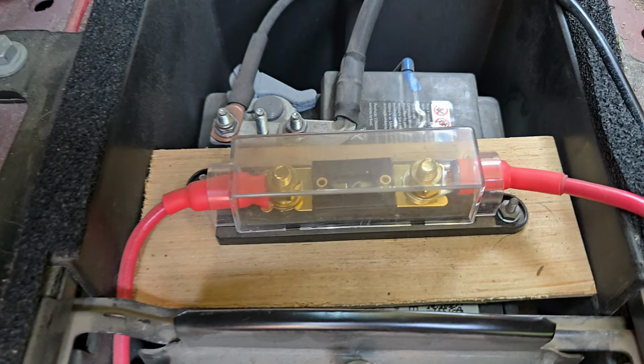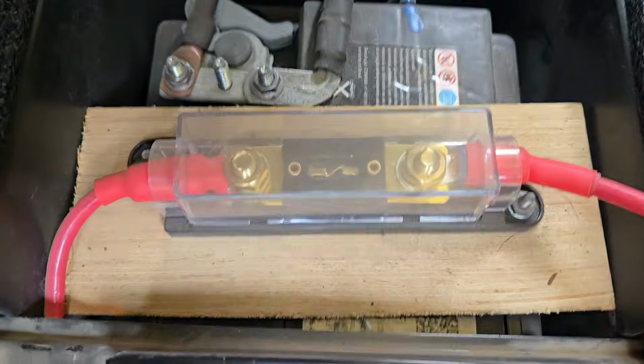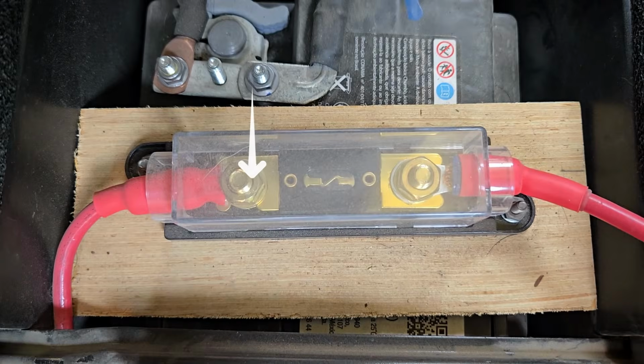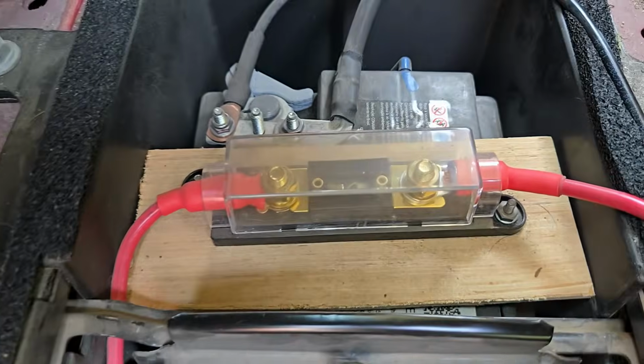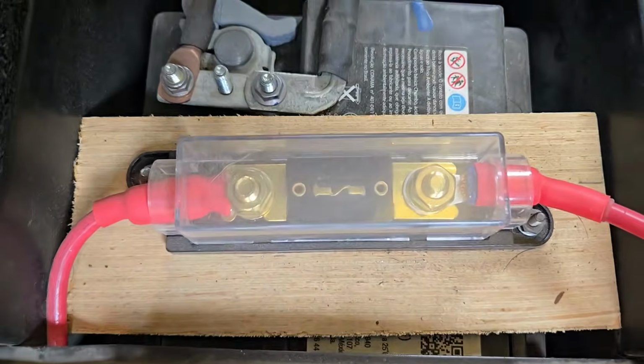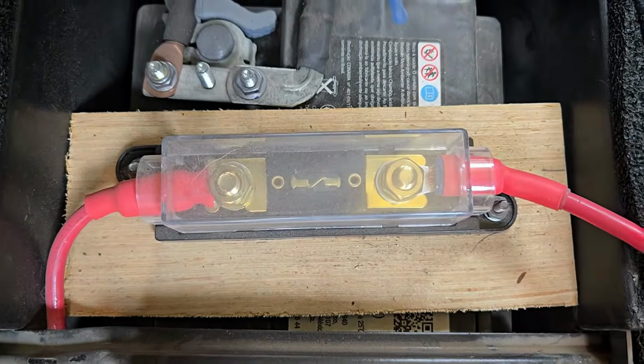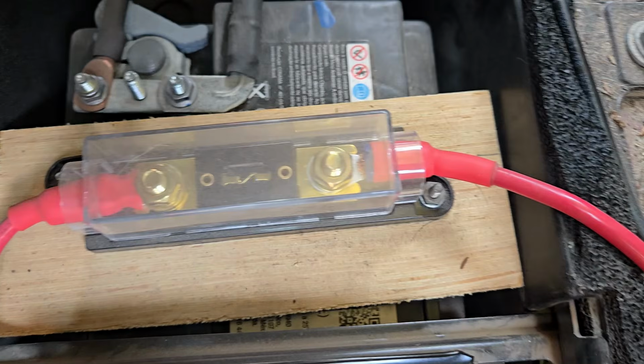Go ahead and snip the positive wire with wire cutters and strip the end. Attach a lug and shrink wrap for a secure connection, then attach the lug to the inline fuse with a washer and nut. Next, run a positive wire from the other end of the inline fuse to the next circuit breaker. Strip back an end of the wire and attach it to a lug using wire crimpers and shrink wrap.